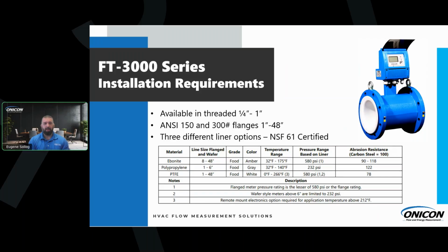Also with this meter, looking at the different install requirements, this meter is available in a threaded version. You can see the picture is the flange, but we have a threaded version from 1/4 inch to 1 inch. We also have the ANSI 150 and 300 pound flanges from 1 inch to 48 inch. This is typically what we're going to be seeing: 150 pound flanges in the HVAC industry. We do see some 300 pound flanges in those high rises like in New York and Chicago.